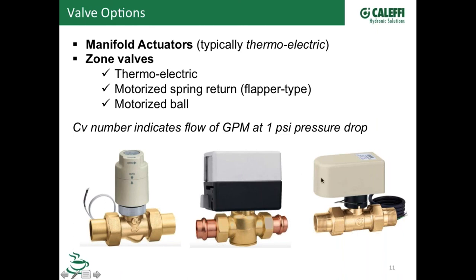And then over here on the right, our 644 series. This is basically a motorized ball valve. So just think of a ball valve when you look in the end of it that we put a motor on. The beauty of that is it's a full port valve, so very high flow. I think that's what, a 13 Cv, Cody, on that valve? I think it's 11, if I remember correctly. 11. But yeah, it's up there for sure. Yeah, so high flow. See, that's why Cody's here today, folks. So we've got a high flow through that, but also a high shutoff pressure. And this will get used a lot of the time on geo pump and dumps where you're trying to close off against the well pump pressure. You might have 50, 60 pounds of pressure. So high flow, high shutoff pressure.